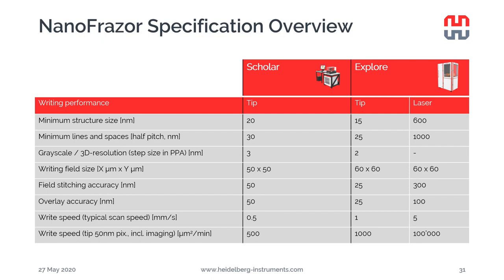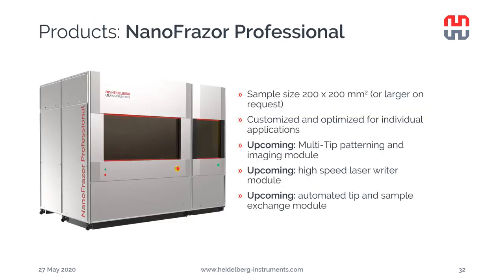Now let's have a look at the specifications of both Scholar and Explore systems side by side. Scholar is more sensitive to the environmental noise, therefore slightly worse numbers. The write speed of Scholar is also slower than the Explore. The minimum structure size of Scholar is specified as 20 nanometer, but you can also write 10 nanometer if you have a quiet environment, because the minimum structure size is rather related to the tip dimensions. With the laser, we are able to demonstrate the minimum structure size of 600 nanometer.